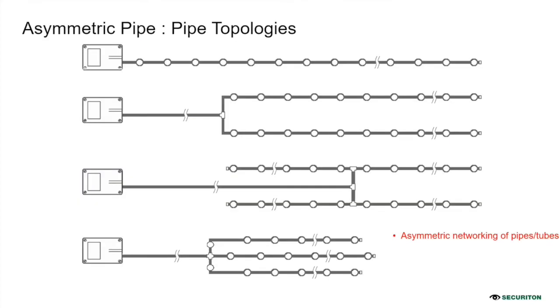Another important part is the asymmetric pipe installation. Why is it important? Because the equipment is not streamlined inside the HVDC, and is installed in a random manner. So we need flexibility in detection, by running tubes in a zigzag or asymmetric manner, so that we can cover the entire hall, entire area, entire equipment. The chances of fire are everywhere in the hall. A lot of tees, bends and joints are required in this kind of area, and that can't be taken care of during commissioning if it is not designed properly in advance.